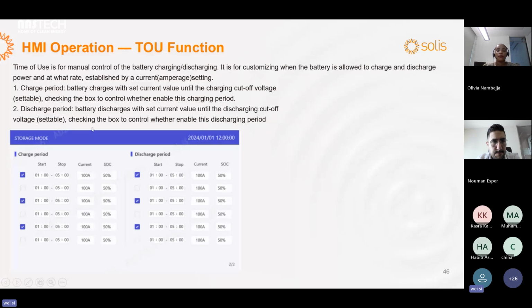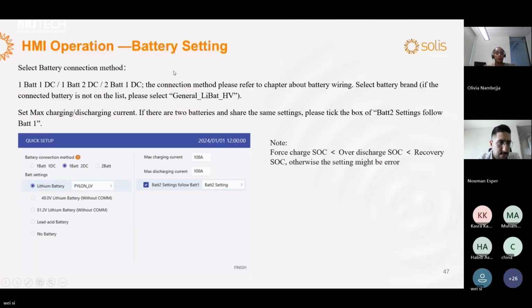It is about the TOU function, so you can set 6 time periods for charging or discharging: 1, 2, 3, 4, 5, 6. For the battery connection, if you only have one battery, you just need to choose one battery, one DC port. If you have 2 DC ports together connected to one battery with a big capacity, just choose one battery, 2 DC ports. Then you can choose the different battery communication protocol.